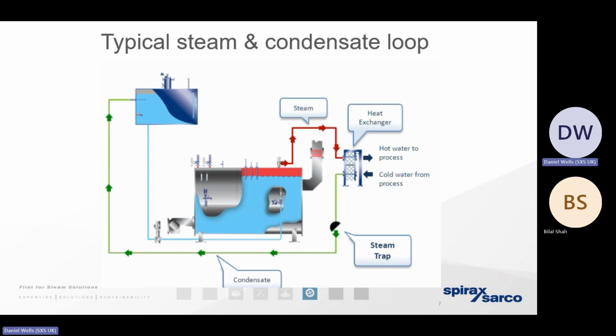As far as the fire tube boilers are concerned, this is what you will commonly find in the hospital up the road. You'll find them in a lot of the food and beverage processors. You'll find them down at the chemical plant down on Leeds Road, for example. The horizontal fire tube boilers, they're really limited by the road network. So if you can imagine one of these boilers being transported down the M62, it's limited by the capacity or the load that is permissible on the road. So you'd be talking about a steam production of approximately somewhere between 25 and 27 tons per hour. So imagine that, between 25 and 27,000 kilograms per hour of steam. And it's by no means unusual for an industrial process to have a bank of up to 6 of those. That might be as big as a 4-berth caravan, physically, round about that sort of size. Potentially even bigger. So you're going to have potentially a 3-meter diameter.